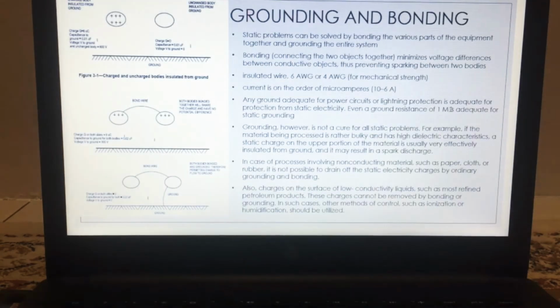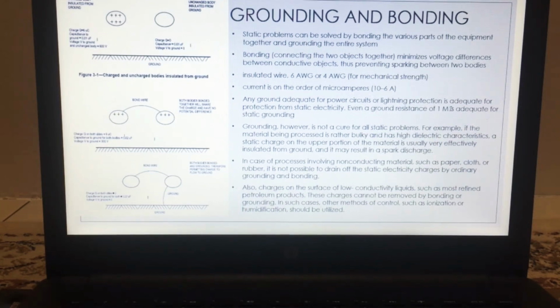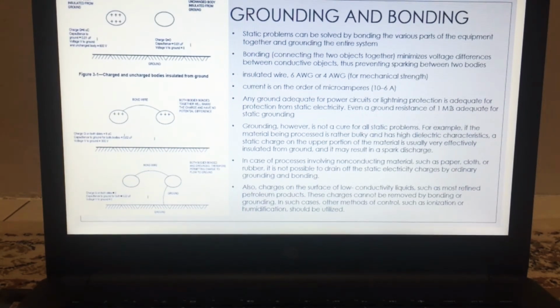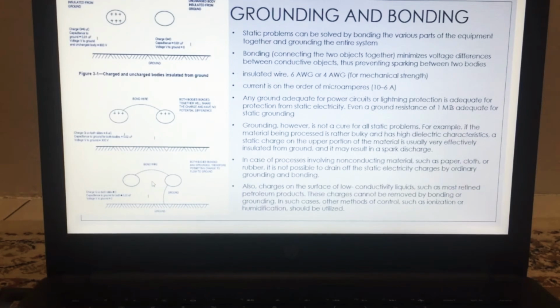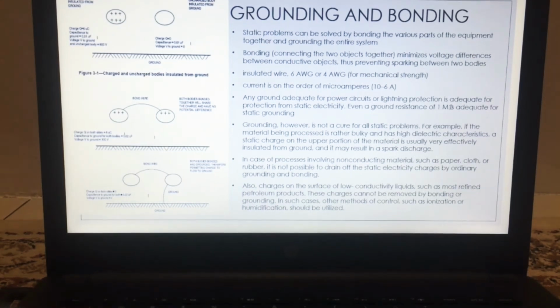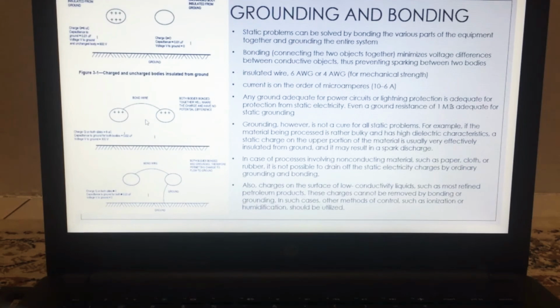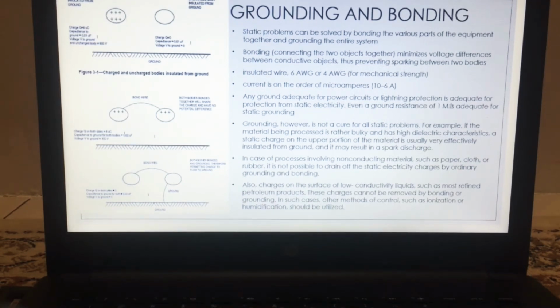So this is the grounding and bonding. Static problems can be solved by bonding the various parts of the equipment together and grounding the entire system. As you can see, it's the last one. Bonding, connecting the two objects together, minimizes voltage differences between conductive objects, thus preventing sparking between the two bodies. This is the one in the middle: insulated wire, 6 AWG or 4 AWG for mechanical strength. Current is on the order of microamperes, 10 to the power of minus 6 amp.